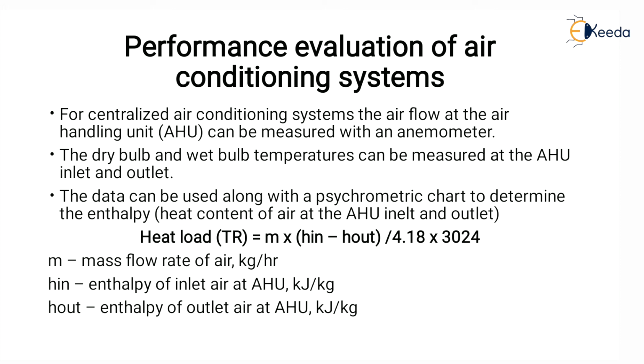Next is performance evaluation of air conditioning system. Here for the centralized air conditioning system, the airflow at the air handling unit, that is AHU, can be measured with an anemometer, and the dry bulb and the wet bulb temperatures can be measured at the AHU inlet and outlet, and the data can be used along with the psychrometric chart to determine the enthalpy. So the heat load is equal to M into H in minus H out divided by 4.18 into 3024. Here M is mass flow rate, H in is the enthalpy of the inlet air, H out is the enthalpy of the outlet air.